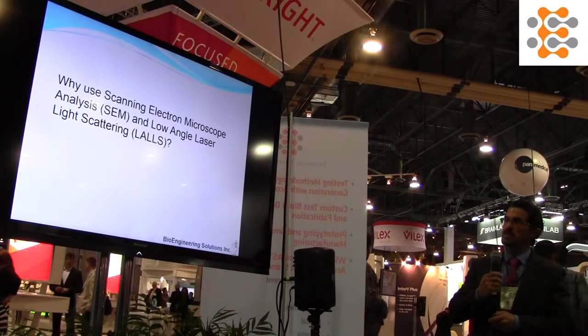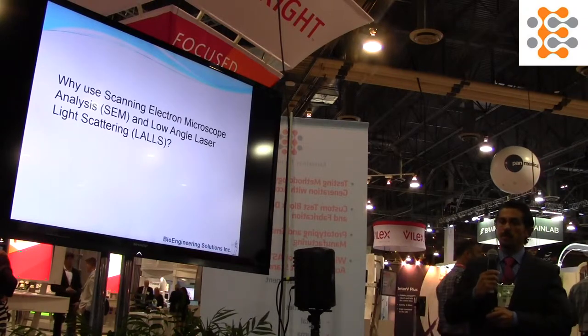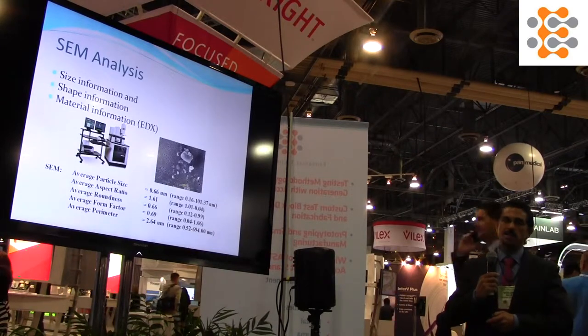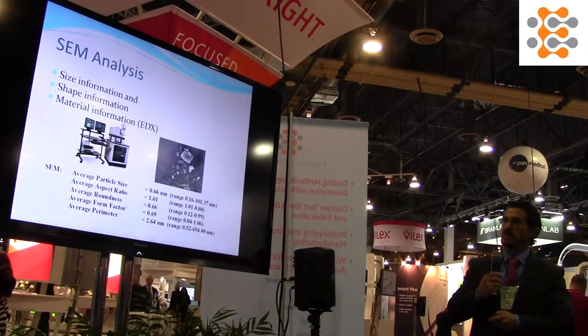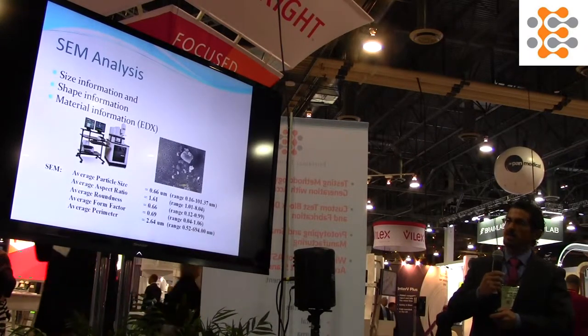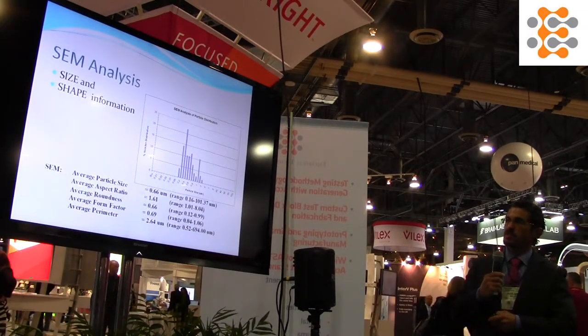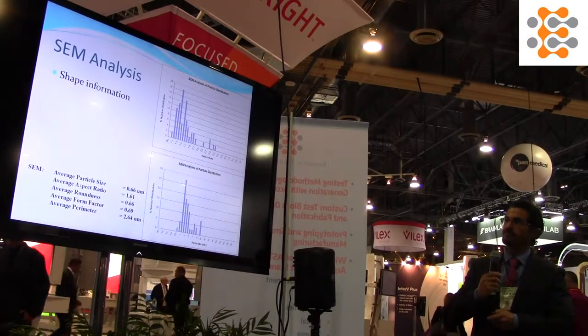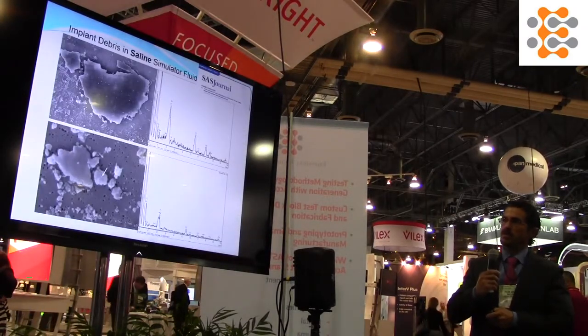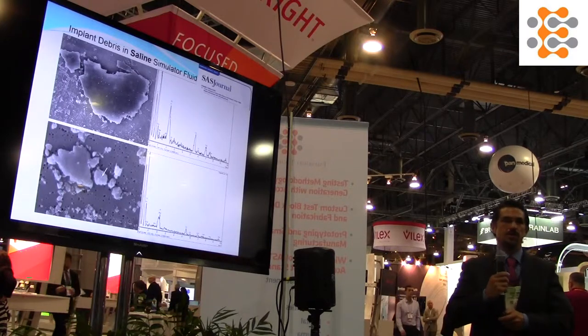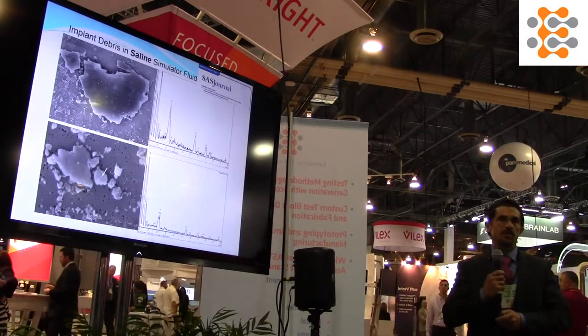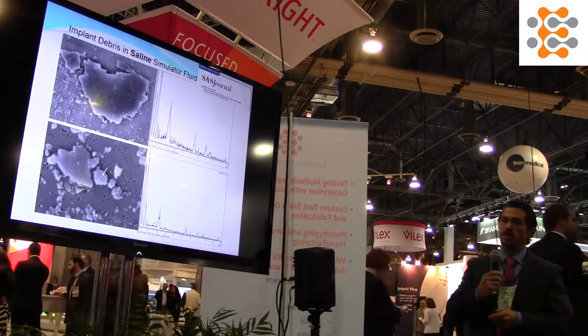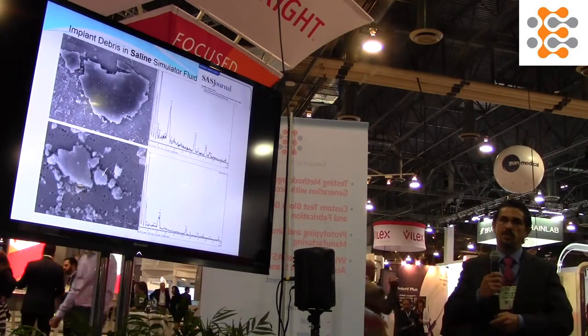Why do you use SEM analysis and low-angle light scattering — both of those together? SEM gives you the size, aspect ratio, roundness, and shape factors that the other technique cannot give you. It gives you distributions in all those ranges, including shape information. It can also look at the chemical signatures of those particles to determine if they were produced from corrosion, simply from wear of the implant, or whether they're from the grips or fixturing or from the implant itself.